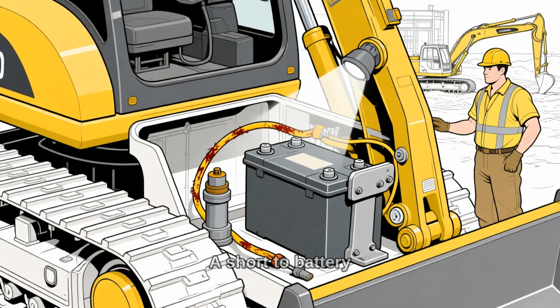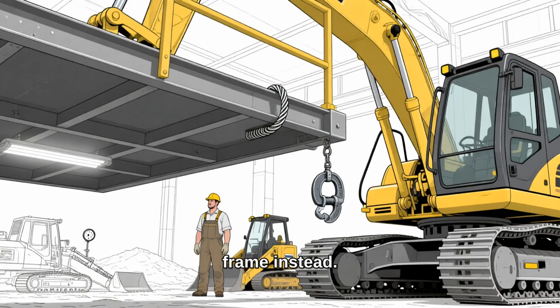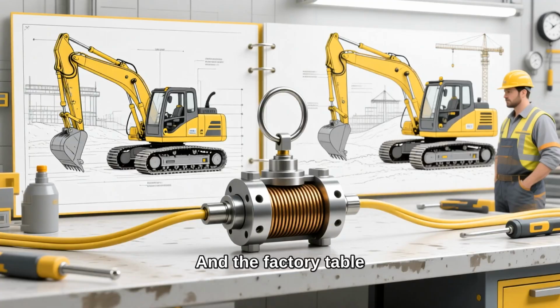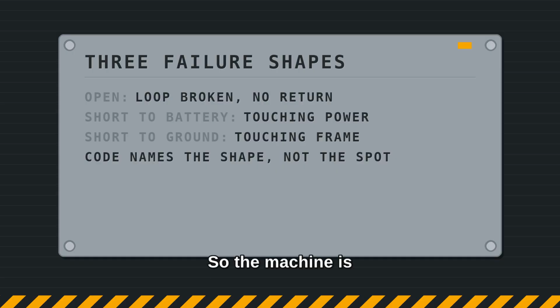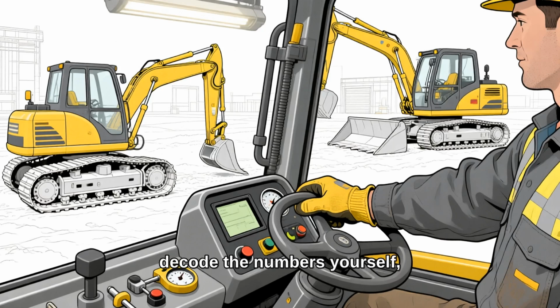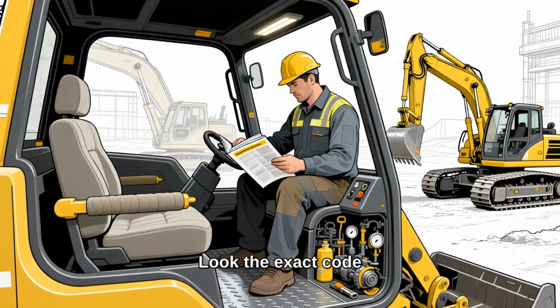Other codes point the opposite direction. A short to battery means a wire's touching power it shouldn't. A short to ground means it's touching the frame instead. Same wire, opposite failure, completely different hunt. And the factory table lists those as separate codes for the same part. The traction lock hold solenoid has both. So the machine is telling you the shape of the failure. Open, shorted to power, shorted to the frame. But don't try to decode the numbers yourself, and don't assume a pattern carries across the table. Look the exact code up. Guessing at the numbering is how people end up rewiring a perfectly healthy circuit.